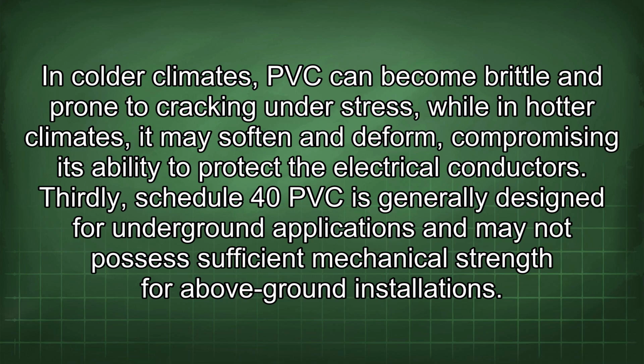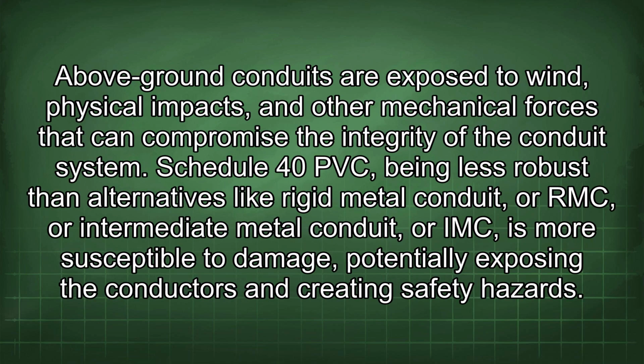Thirdly, Schedule 40 PVC is generally designed for underground applications and may not possess sufficient mechanical strength for above-ground installations. Above-ground conduits are exposed to wind, physical impacts, and other mechanical forces that can compromise the integrity of the conduit system. Schedule 40 PVC, being less robust than alternatives like rigid metal conduit, or RMC, or intermediate metal conduit, or IMC, is more susceptible to damage, potentially exposing the conductors and creating safety hazards.